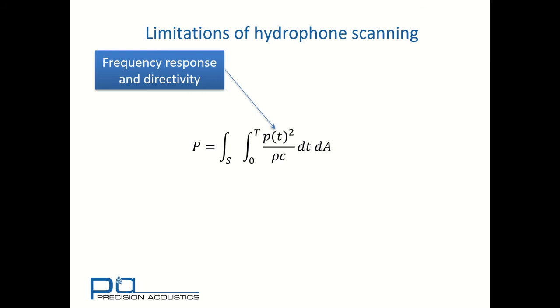If you're less familiar with these topics, there are additional PA tutorial videos on frequency response, directivity, and the conversion of voltage to pressure signals. That hydrophone will have a calibration uncertainty. This is typically at least 10% and often higher.